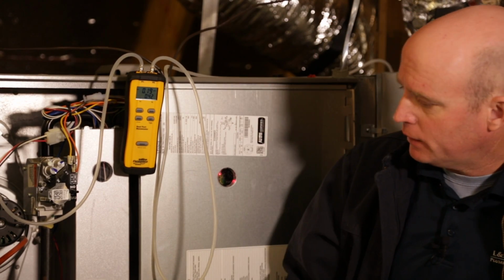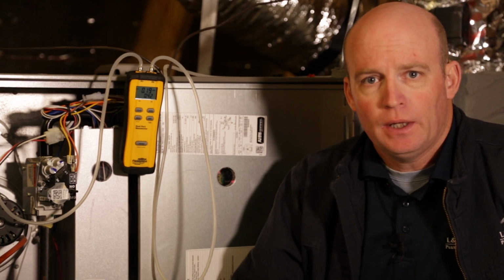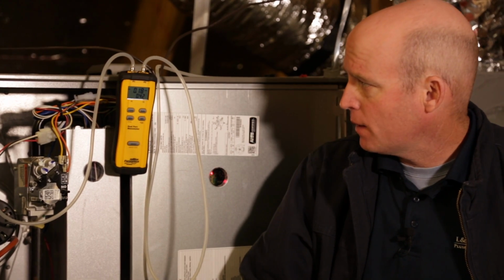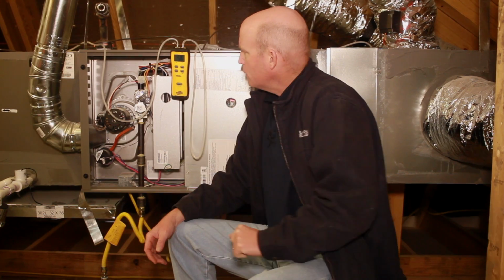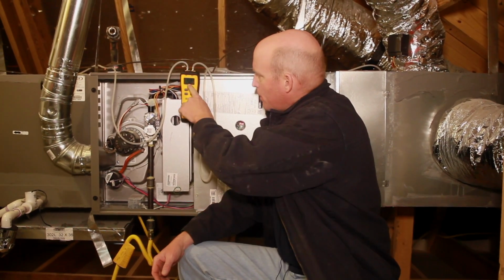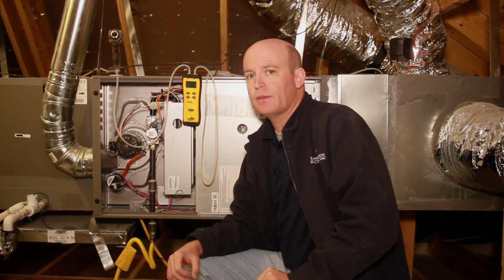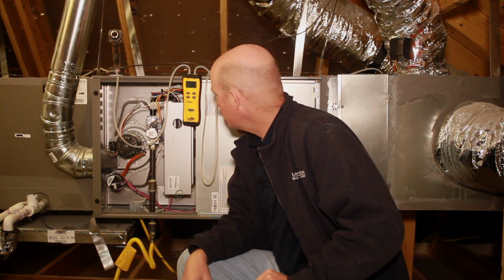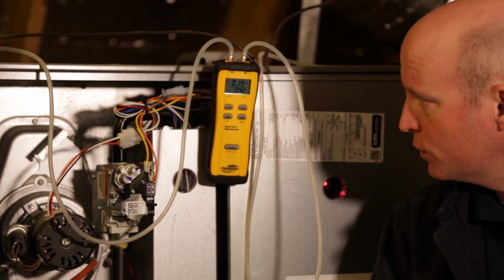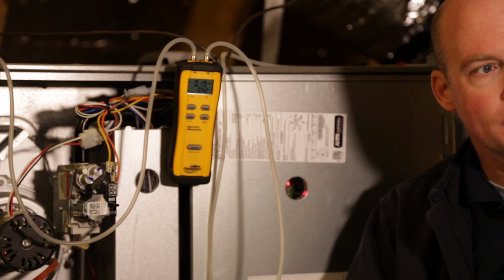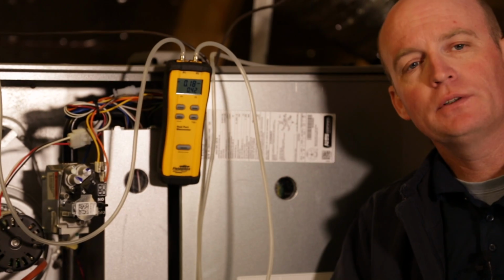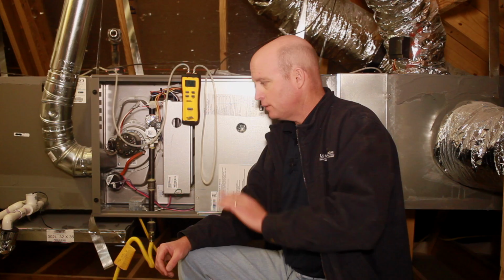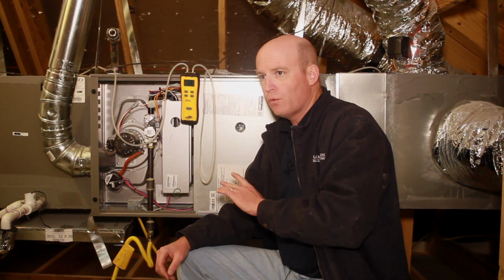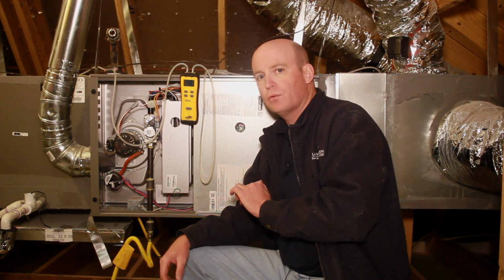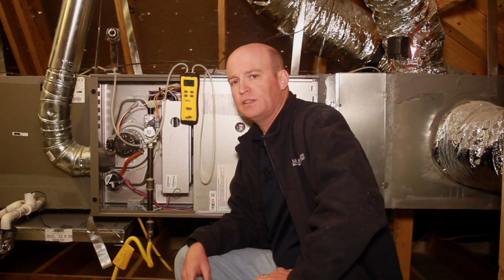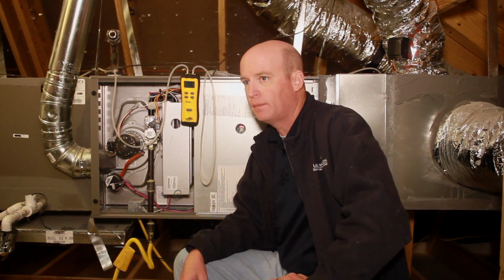Okay, our equipment is up and running now. We have our blower set at a steady RPM, and we're going to go ahead and take a look at our manometer. The top number is one hose only. The bottom number is where the manometer has done the math for us. So we know our total inches of water column is 0.42, 0.43, somewhere just a little bit above 0.4. Now we've looked at a blower table, and we know that at this given speed at 0.4, somewhere between 0.4 and 0.42, we're running approximately 1700 CFM.